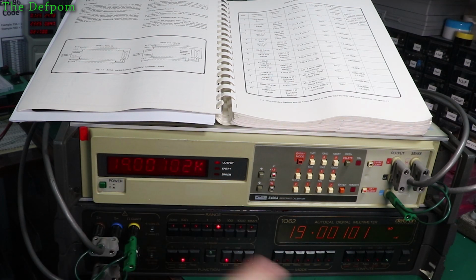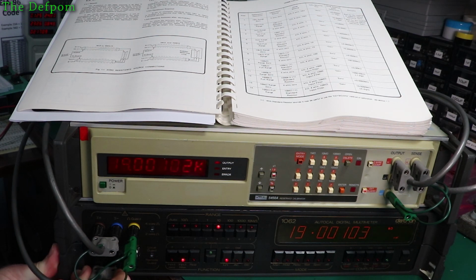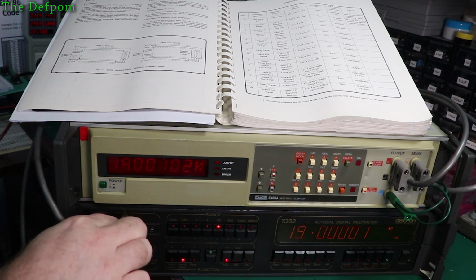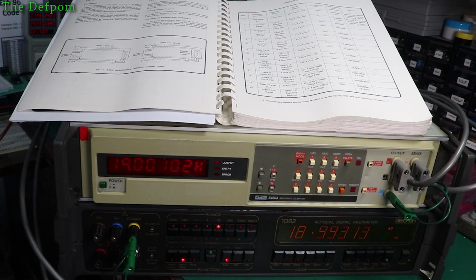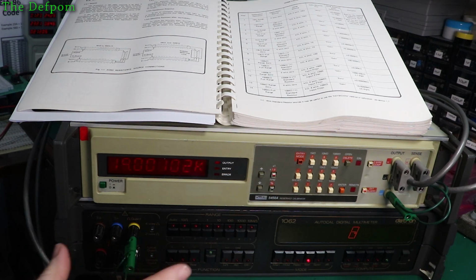102. It's getting it, with a little bit of noise affecting it. That's not bad. Okay, so let's do a self-test. Let's unplug these things in case it matters, and do a self-test on this. I think I'm going to do a self-test in calibration mode. If it doesn't fail, that's great. What I'll do is a calibration basically against the 19 range rather than the 10 range.